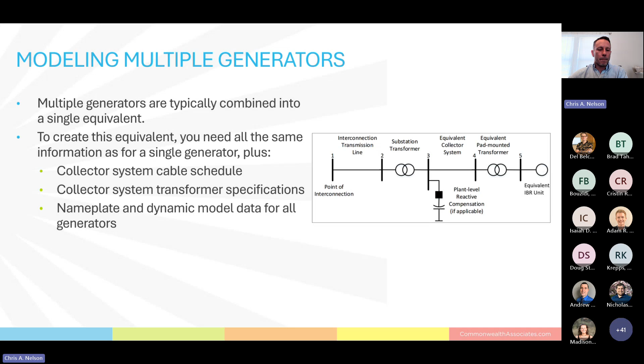If you have, let's say, five megawatt generators, you can add a 5 or 25 megawatt generator and a 25 or 30 megawatt transformer, or whatever MVA. But the cables get a lot more complicated, because a lot of the time they're daisy chained, and a lot of the time they're not. The cables are different sizes, so you can't just add the impedance up. There's some pretty complex math that goes into that.